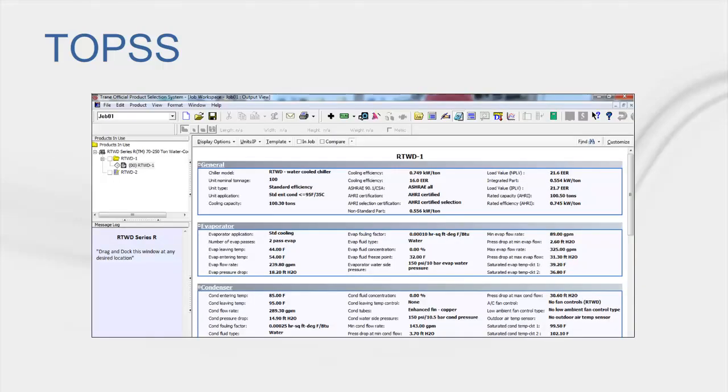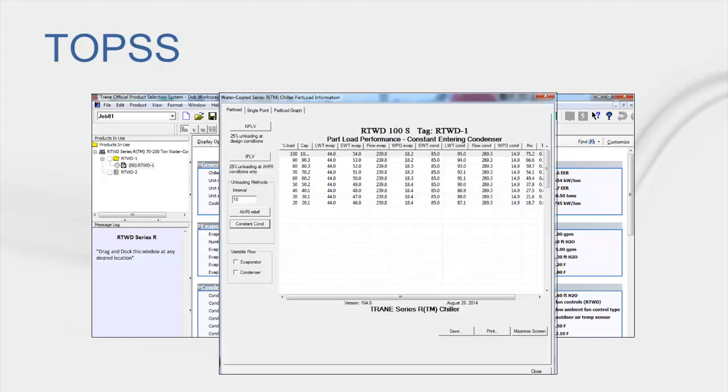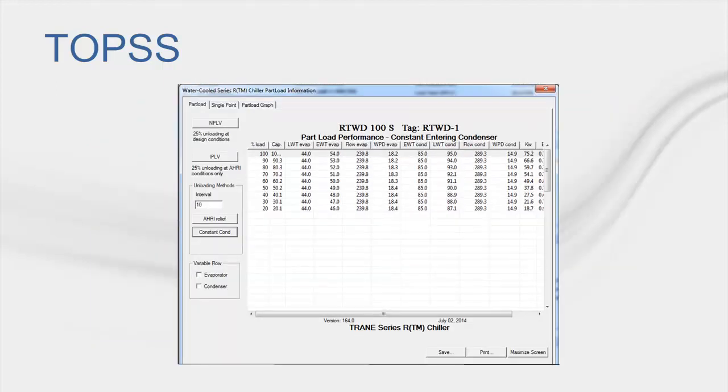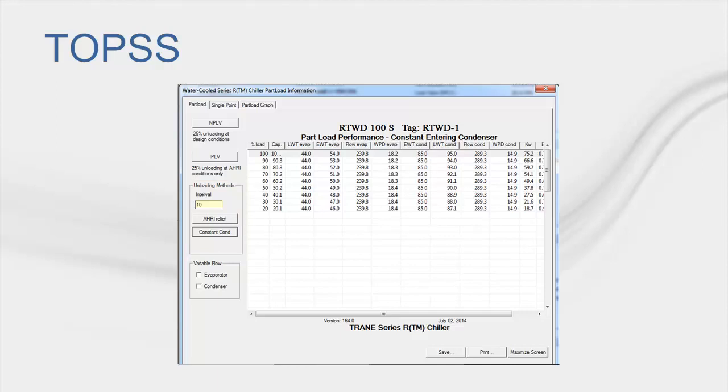Moving on, you can see here that I have selected an RTWD Water Cool Chiller within TOPSS. Now that I have a valid selection for this product, I can click on the View Graphs and Charts Toolbar icon. Clicking on this option brings up the following window. The data that we are looking for to create the Power Consumption Curve can be accessed by referring to the Unloading Methods section on the left-hand side of this window. The interval is conveniently set up to provide the data in 10% steps. Clicking on the Constant Condenser button populates the table with the data that we are looking for.